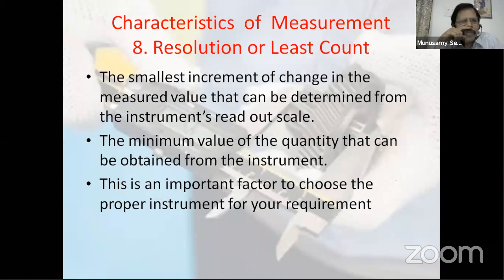Now, this is one most of us have done in our laboratory: the least count or resolution of an instrument. It is the smallest or least value that you are able to measure using the instrument's readout scale. The smaller the value you want to measure, the more that decides whether the instrument is usable or not. So there's a minimum value of the quantity that can be obtained from the instrument. You define it as the least count or resolution. Based on the requirement in your experiment or application, you have to choose a proper instrument. Choosing a very big range instrument, where a smaller value is not going to be helpful for you, is not going to be possible.